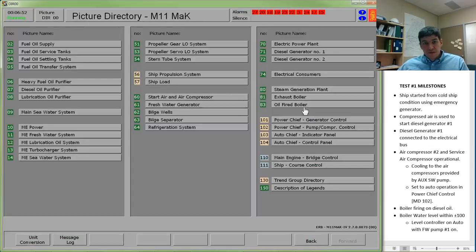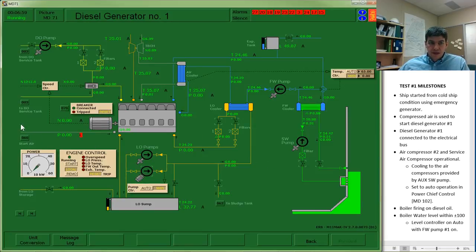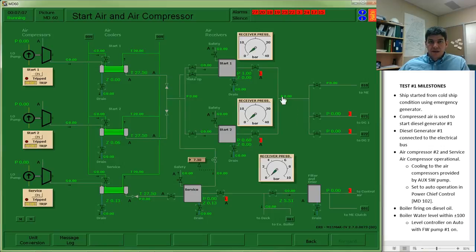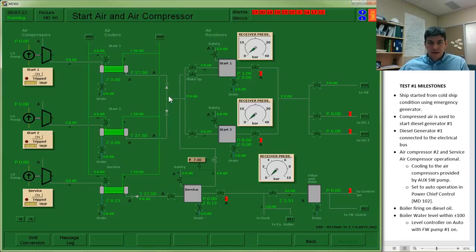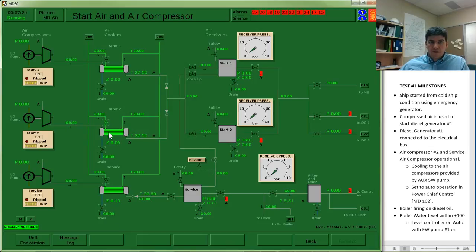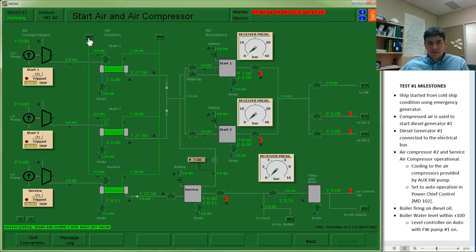First place I'll go is diesel generator number 1 and observe that in order to get this running I will need my start air system up and running. My start air system pathway is going to come back and I will supply it with my start air compressor number 2. Before I get this thing started, I want to establish cooling water. I will need to open up this valve to get water through the after cooler on the air compressor number 2. However, when I open up that valve, you see there's no flow.